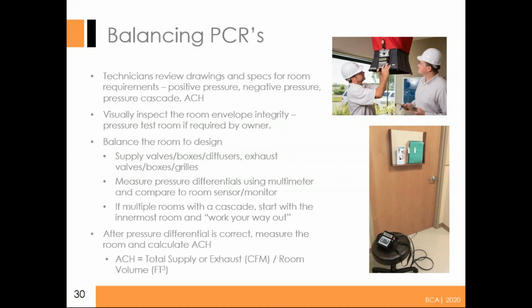negative. After you've got a handle on your project, what you're trying to achieve, usually inspecting the room is always something that you need to do, go around looking for the various little things that possibly may have been missed during the construction and setup phase. But for instance, if we're going to go for a positive room, what we've got to remember, our dominating factor is the supply. So a lot of times you're going to get those set up as far as your supply numbers, because the room's got to be positive. And typically the numbers that are being put on the return, as far as the returns or the exhaust, I don't want to say they're a guess, but once again, going back to the previous stuff, it's a baseline. Knowing that our supply, being a positive room, is pretty well etched in stone to maintain our air changes per hour and so forth. So our variable in a positive room, after we get it set up, would be the exhaust. So you get your supply set up to your design, you set your exhaust up for your design.